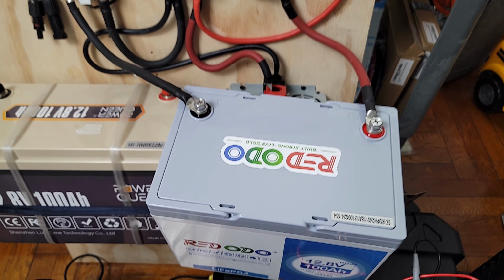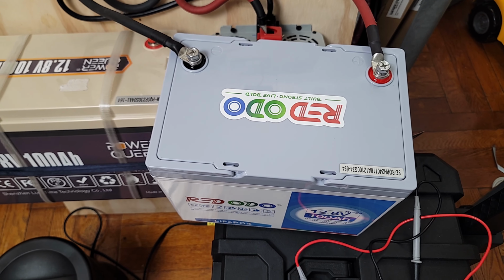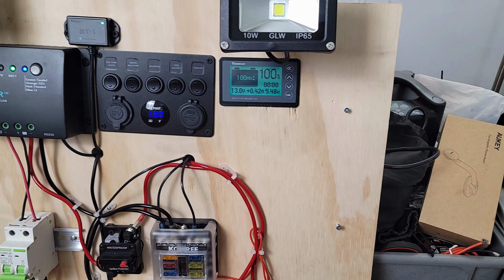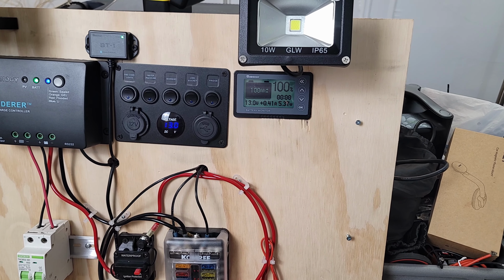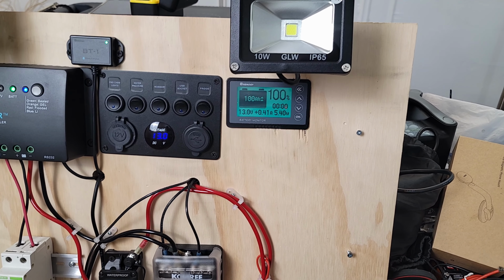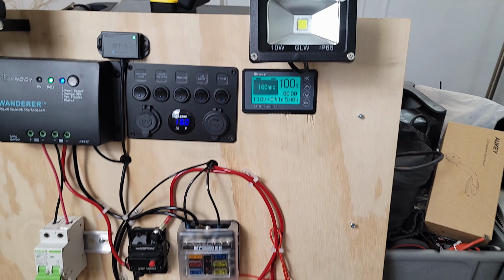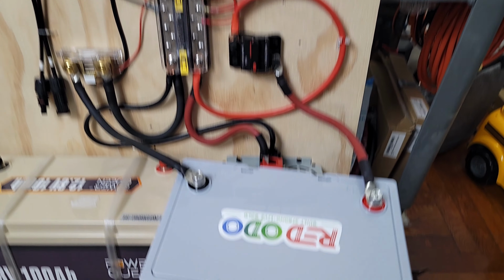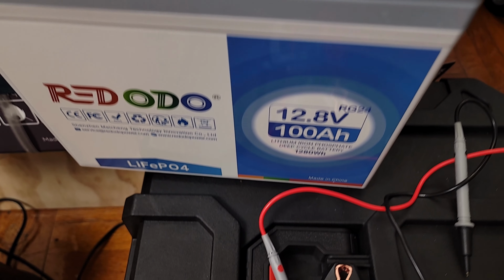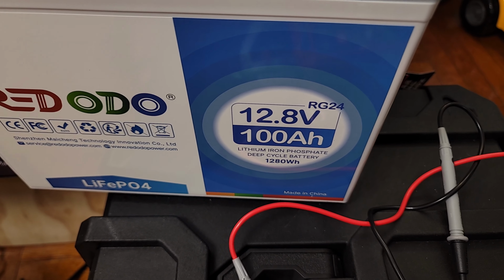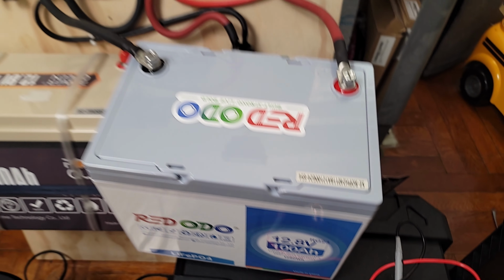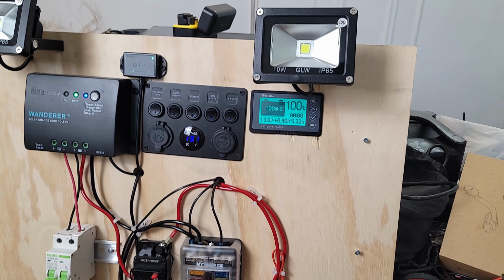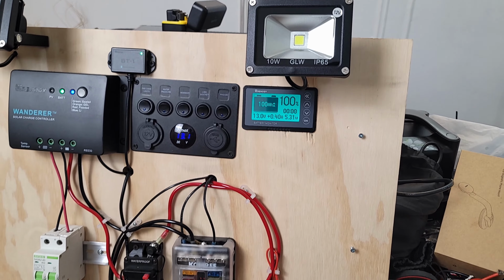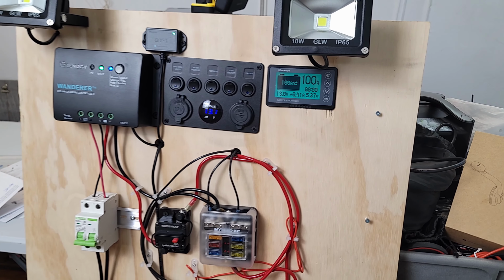For now, I'm blown away. I'm happy to see that the inverter held its own for 1.3 kilowatts, which is 1,300 watts. The total peak here says 1,280 watt hours. So on the manual, I believe it said 100 amps maximum, so about 1,200 watts, and then you have the 1,000 watt inverter.